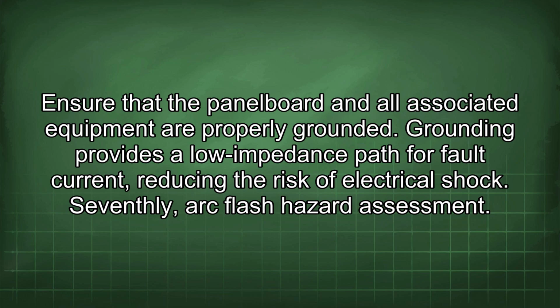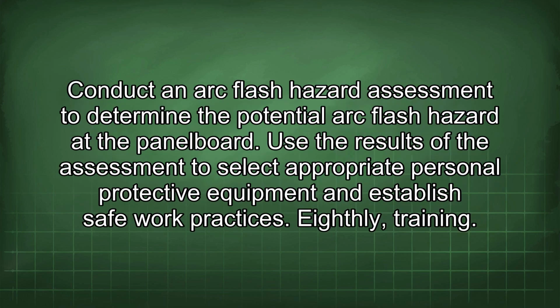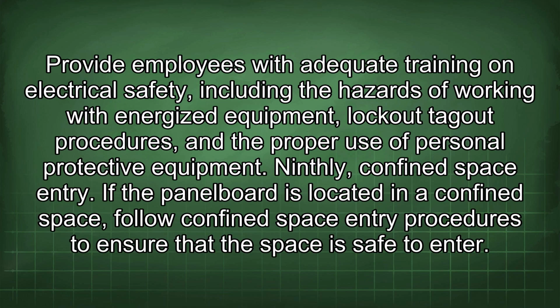Seventhly, arc flash hazard assessment. Conduct an arc flash hazard assessment to determine the potential arc flash hazard at the panel board. Use the results of the assessment to select appropriate personal protective equipment and establish safe work practices. Eighthly, training. Provide employees with adequate training on electrical safety, including the hazards of working with energized equipment, lockout-tagout procedures, and the proper use of personal protective equipment.